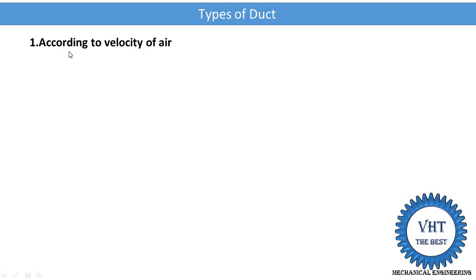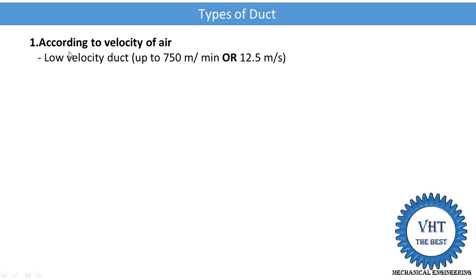The first classification is based on the velocity of the air. On the basis of velocity, it is classified as low velocity and high velocity duct. The low velocity duct is one in which the velocity of the air is up to 750 meters per minute, which is equal to 12.5 meters per second. In the high velocity duct, the velocity of the air is greater than 750 meters per minute, or greater than 12.5 meters per second.